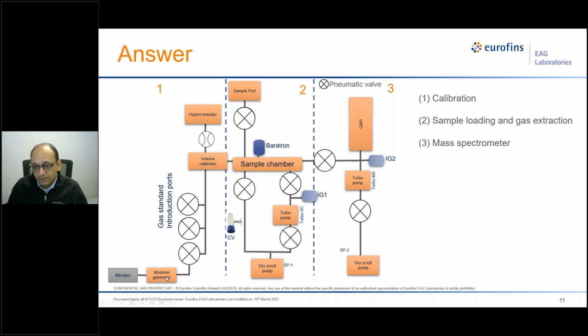However, if you look carefully, that entire gas line is connected to the volume calibrator as well as forwarded towards the hygrocomputer. The hygrocomputer is another independent device that measures the moisture in this gas. So the moisture generator is generating nitrogen and moisture for us, and it is calibrated, so it is giving us a known amount of moisture, but we are required to independently measure the moisture in the mix that is being introduced to the sample chamber. So the hygrocomputer's function is to confirm the moisture content in the gas being exposed to the sample chamber.